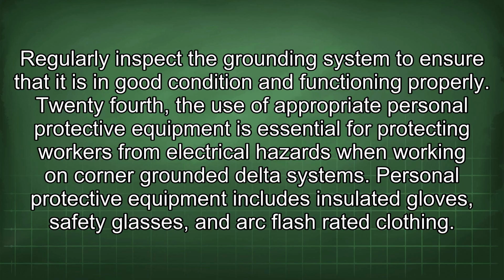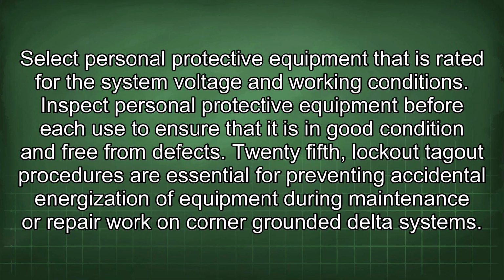24th, the use of appropriate personal protective equipment is essential for protecting workers from electrical hazards when working on corner-grounded delta systems. Personal protective equipment includes insulated gloves, safety glasses, and arc flash rated clothing. Select personal protective equipment that is rated for the system voltage and working conditions. Inspect personal protective equipment before each use to ensure that it is in good condition and free from defects.